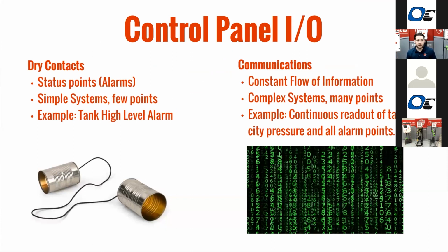Okay. In terms of the inputs and outputs, they kind of go hand in hand with the relay logic versus the PLC or the dedicated controls. So our dry contacts are going to be single points of information, on, off, things like that. All of our control panels are going to have what we call a fail-safe dry contact in them. Basically that's going to give you an alarm output to the building automation if there's actually an alarm. It's also going to show as an alarm if we lose power or control power. Having it be a normally open contact that we have to hold closed all the time is significant, because that way they're getting an alarm even if we have a system failure that's not necessarily an alarm condition. That's still going to register as an alarm.